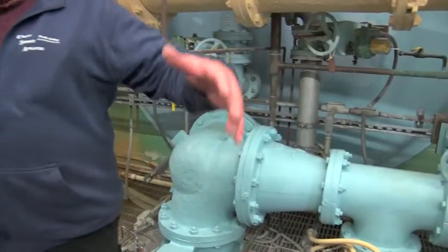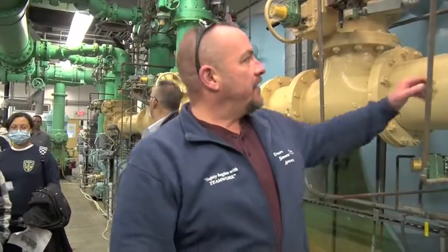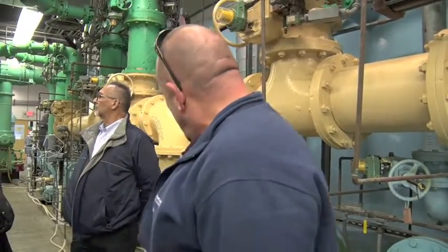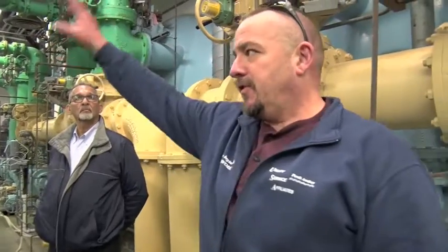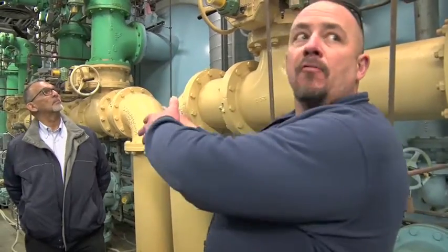During the backwash process, we use close to 30,000 gallons of water, which comes from that tank out in the back. The water comes in from that tank and basically does it backwards, where it goes in from the bottom and then pushes out from the top. It comes through these headers, goes out into a collection system where it goes into those two lagoons that you guys see in the back, where the sludge settles. And from that point, the clean water decants over to the pond on the right, where it goes back to the head of the plant to be retreated. So it's a recycling process.